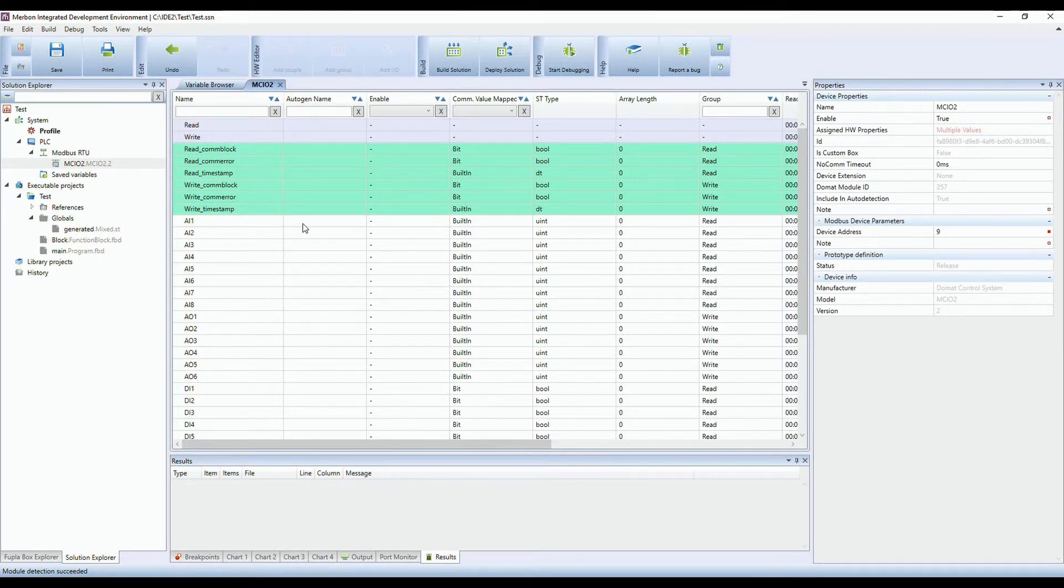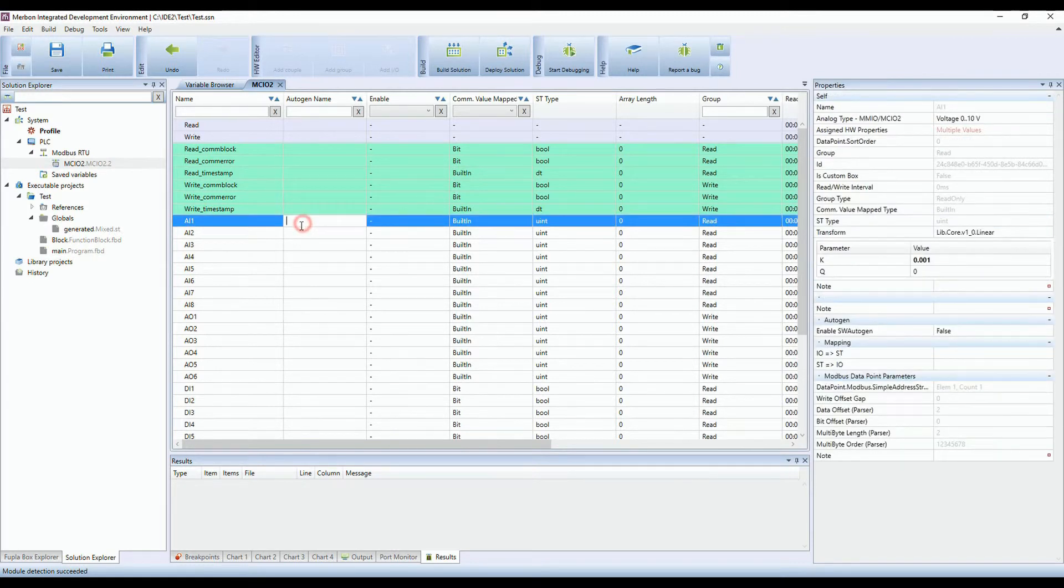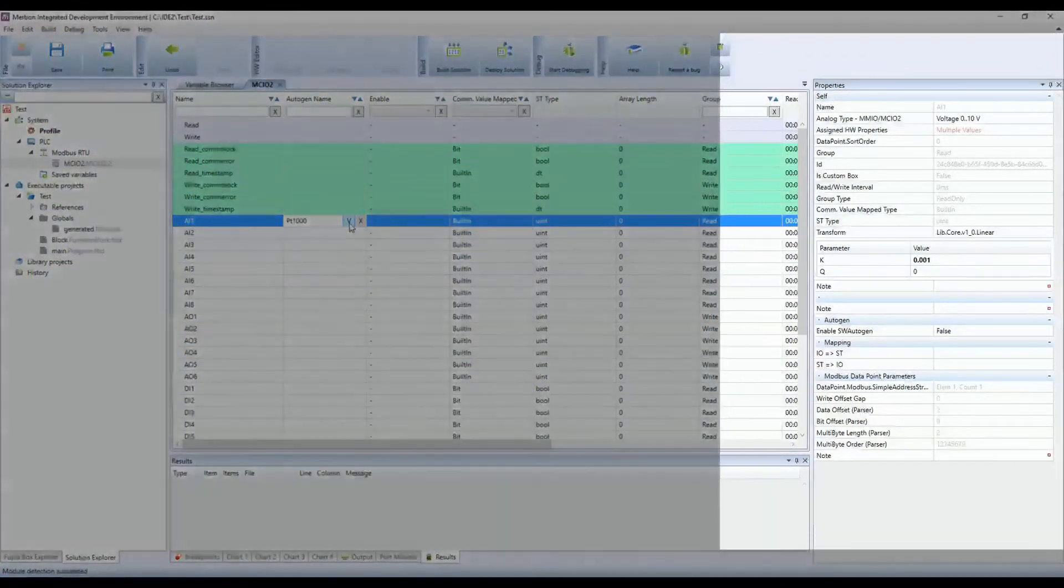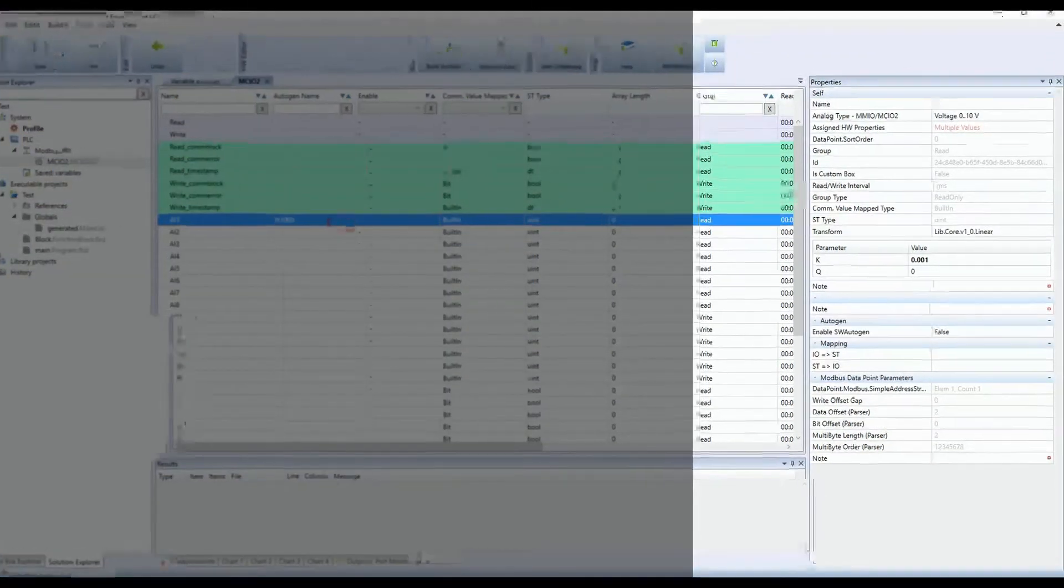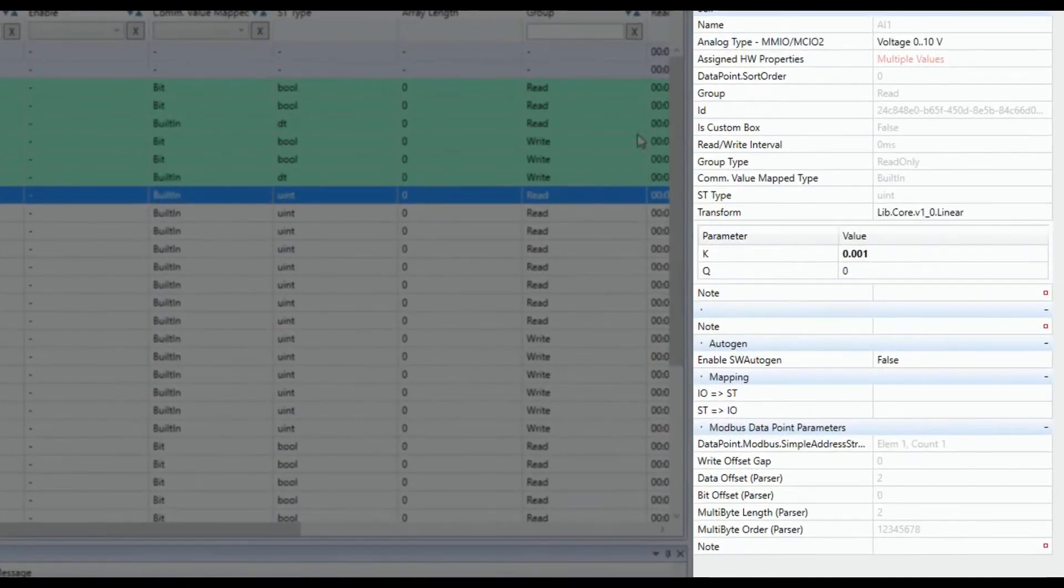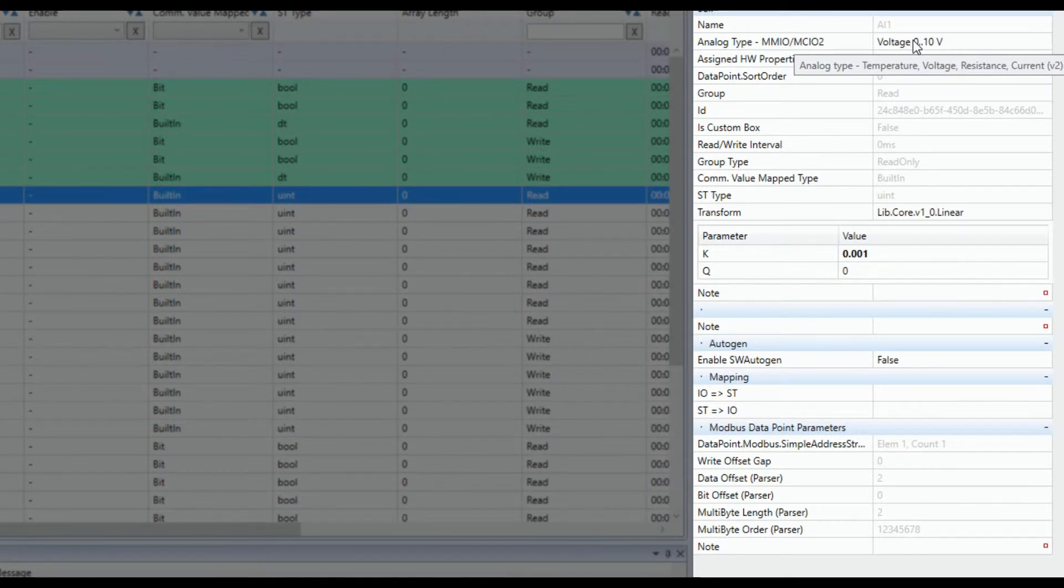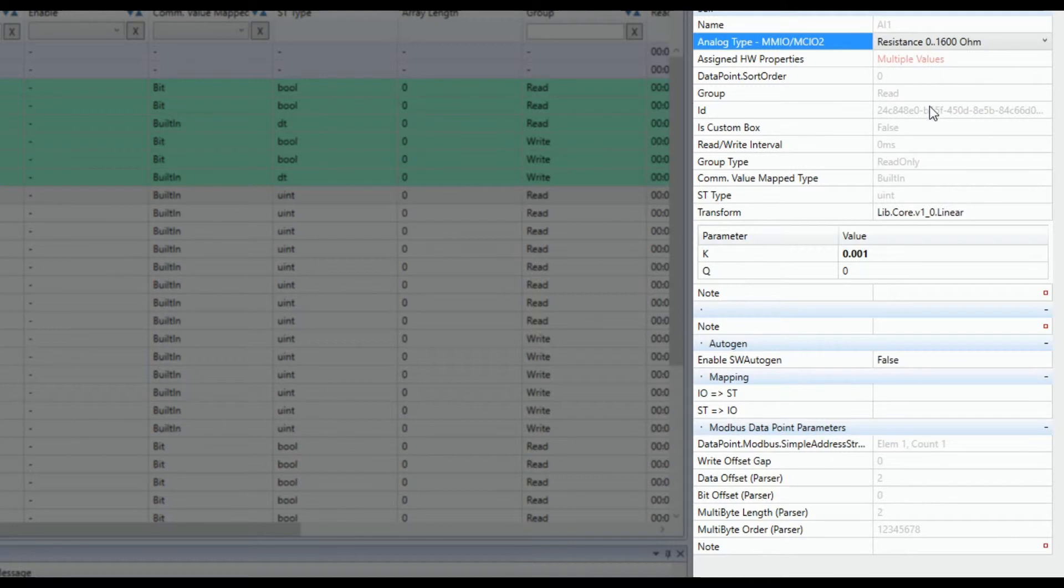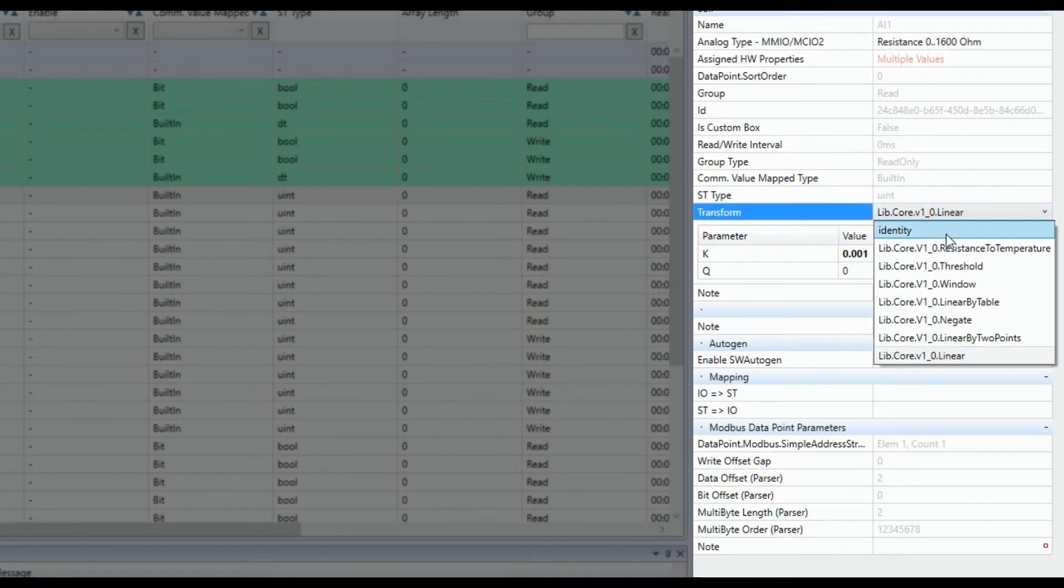If you want to use, for example, temperature sensor PT1000 on analog input 1 AI1, you have to change parameters of this input. Default setting is to measure voltage 0 to 10 volts. You can read either the PT1000 temperature or, as in this case, measure the resistance in range 0 to 1600 ohm.